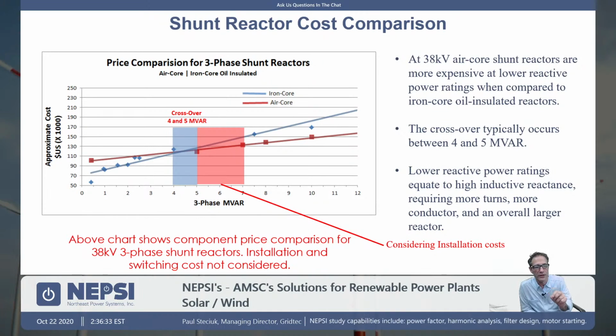There is an installation component to this too, and I put that shaded area in red. That crossover point actually will be pushed to the right a little bit if you start to think about the cost to install those air core reactors, because they can get quite large. If you're in a high seismic zone area, you have to then consider the footings and the cost of the footings and the elevating structure. They can also get very expensive. The iron core reactors are sitting at the ground level, and you don't have as much of a difficult time dealing with the seismic related issues when you're dealing with those high seismic zones.